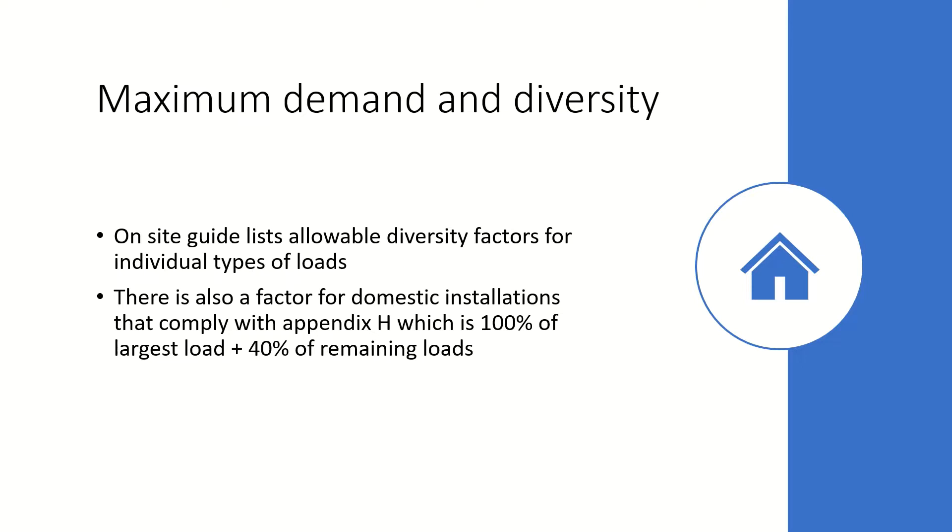One method is to apply diversity to individual loads which I will talk about in another video. In this video I'm going to provide an example of a maximum demand calculation for a domestic installation with a standard circuit arrangement in accordance with Appendix H of the on-site guide.